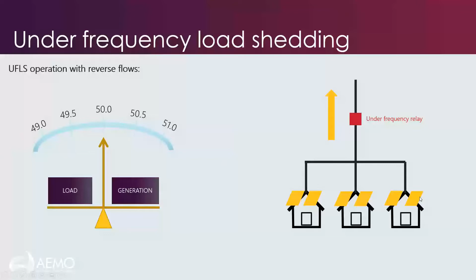And even further, if we now have more PV on that circuit and the circuit is operating in reverse flows, as frequency drops, the relay will still detect that and it will still open the circuit, but now it's disconnected something that was a net generator rather than a net load, and that will actually send frequency further down. So it will actually exacerbate the frequency disturbance rather than helping to correct it.